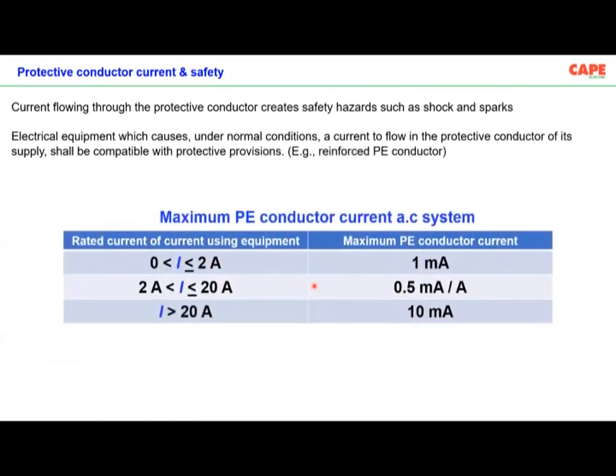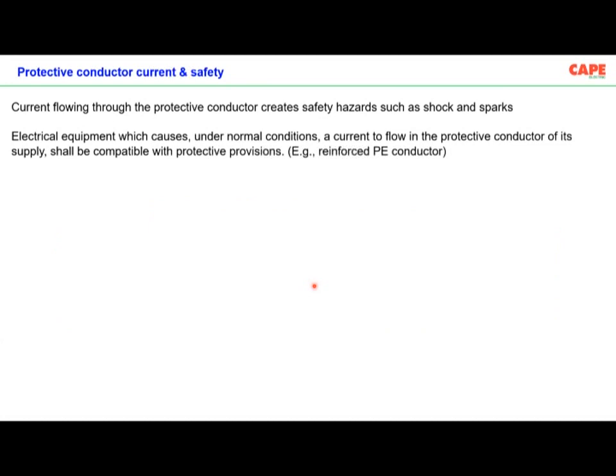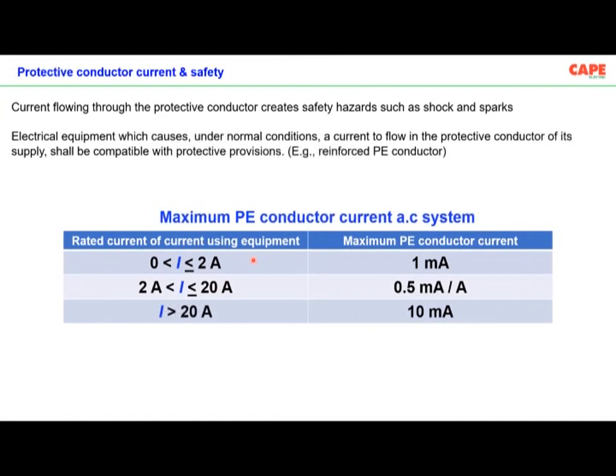Now, the next subject. So far I was explaining about the earthing, how you should make the earthing in an installation. The second part is what kind of wires or what kind of safety are required. Say, for example, protective conductor current. What is a protective conductor? A protective conductor is an earth wire. Different protective conductors are there, like PE conductor, PB conductor meaning protective bonding conductor, earthing conductor, and so on. Now, the maximum amount of PE conductor current in an AC system is, you can see here, for a line current of up to 2 ampere, the maximum leakage current expected in a protective conductor, that means an earth conductor or a green and yellow wire, is 1 milliampere. For load more than 20 amps, the maximum current expected in your protective conductor is 10 milliampere.